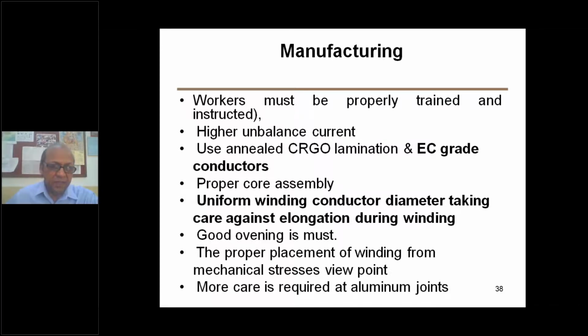Then you have used annealed, no doubt. You use EC grade conductor, there is no problem. But sometimes for the bus bar, if EC grade conductor is not used, then there is going to be a failure, because the bus bar does not cost much. I have seen one failure in the short circuit only because of this reason. They used commercial grade copper unknowingly because they got it from the market. For the bus bar, they used commercial grade copper, and that only melted during the short circuit. That is the reason for the failure.